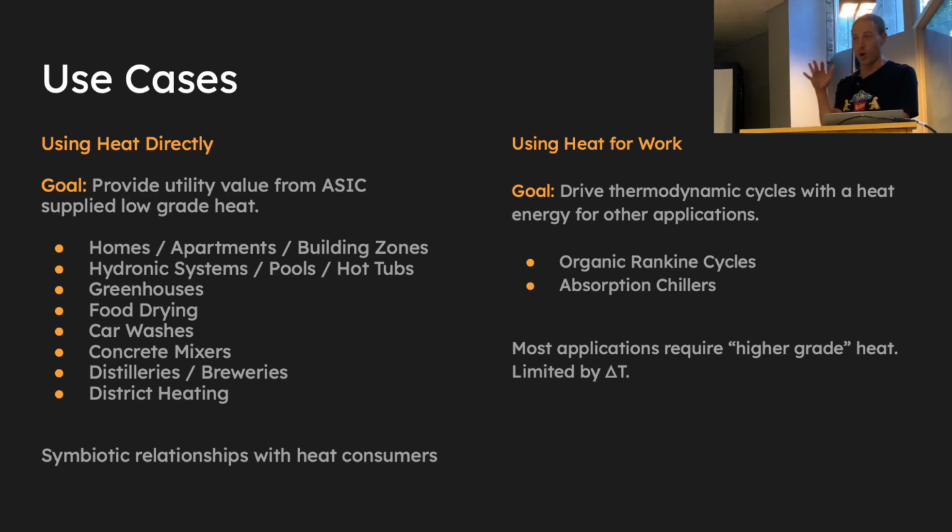The challenge here is the overlap. Usually they want 70 to 80 degrees Celsius as the inlet temperature. And so that's a big one, right? Because that's just above the upper bound of what Bitcoin miners exhaust in terms of liquid cooling from hydro or immersion systems. So it's like just in sight, right?